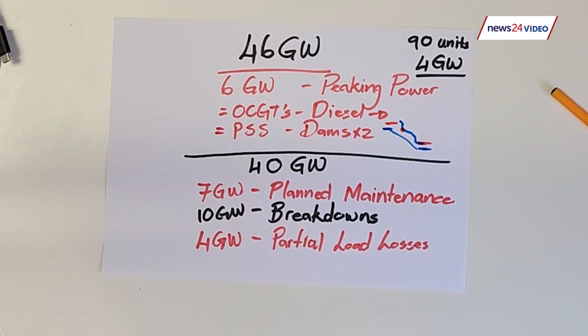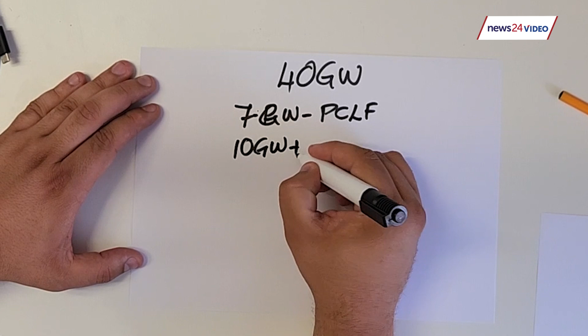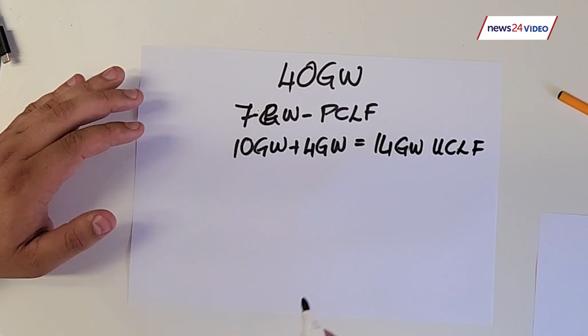Now, those who passed maths in high school will be able to tell us that 46 minus 6 leaves us with 40. So this is 40. That's what's left after you take away the peaking power stations. Then we've got 7 gigawatt of planned maintenance, PCLF, planned capability loss factor. You've got 10 gigawatt plus 4 gigawatt. That's your breakdowns and your partial load losses to give you 14 gigawatt unplanned capability loss factor.